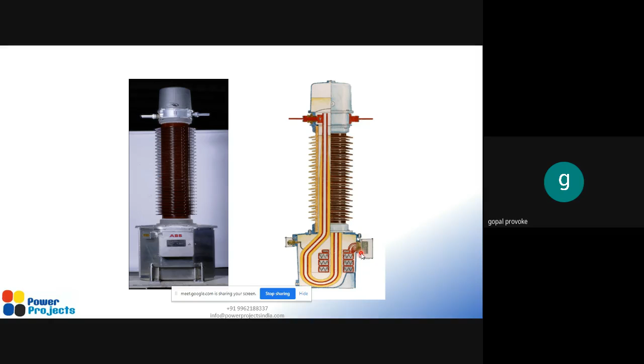Here we have a terminal box, and from this terminal box we will be able to access the current. For example, if we have 1000 ampere here, this will be proportionally converted to 1 ampere. If the primary side is carrying 1000 ampere, in the secondary we will be having 1 ampere. If the primary is carrying 500 ampere, we will be having 0.5 ampere. So proportionally we will be getting a secondary current, and this secondary current will be connected to energy meters and protection relays.